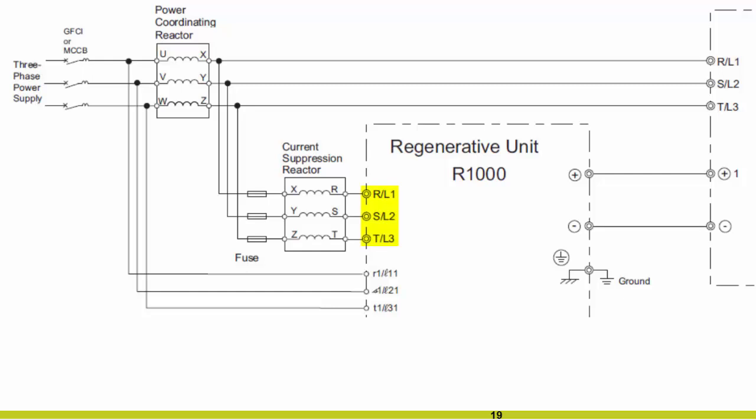The capital RST terminals are the power supply inputs. These terminals power the R1000. Now, despite them being called inputs, they are also outputs. This is because this is where the regenerative power goes back onto the line. To clean up the regenerative power, in line with that is a current suppression reactor and also some fuses for protection. The power coordinating reactor is wired before the fuses. The second set of the input terminals, lowercase r1, lowercase s1, and lowercase t1, are used for detecting phase order. Notice how these wires are landed before all of the reactors. These wires are necessary so that the R1000 can properly apply the regenerative energy back to the utility with the correct phasing.